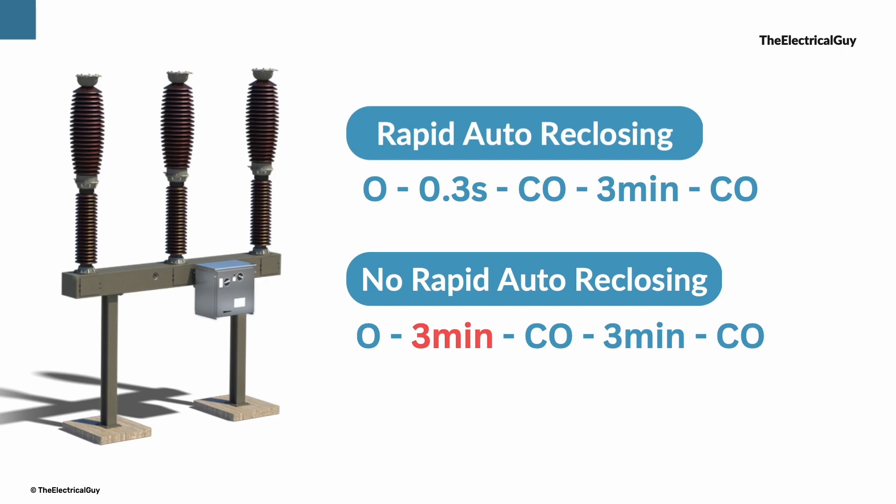If the first timing is 0.3 seconds, then it means it is for rapid auto reclosing. And if it is 3 minutes, then it is not meant for rapid auto reclosing. Just take a note of that. These auto reclosing cycles are defined by the different standards. Like this one is defined by the IEC standards. IEC also defines one more duty cycle which you can see on your screen.